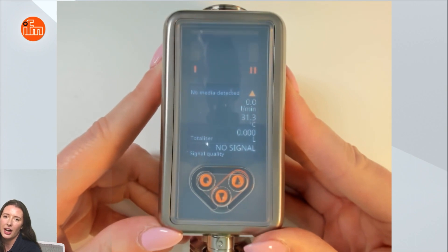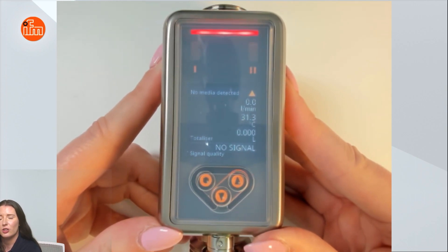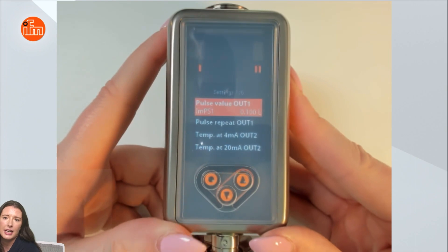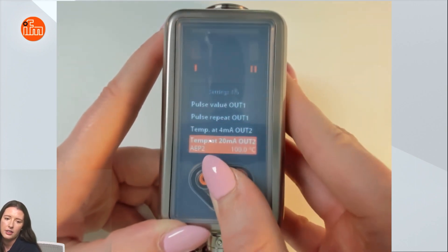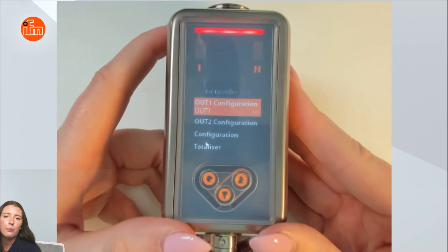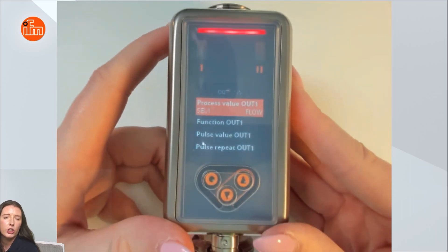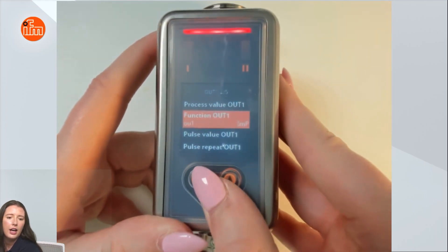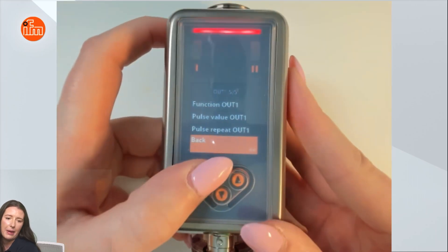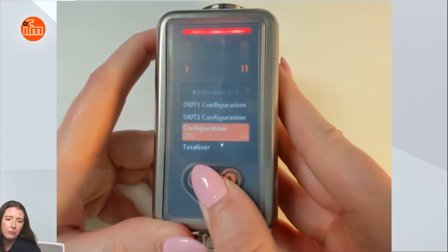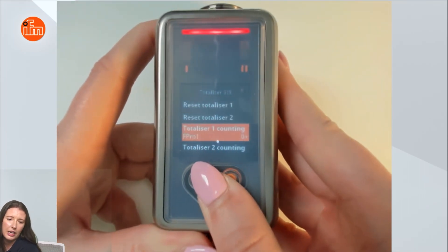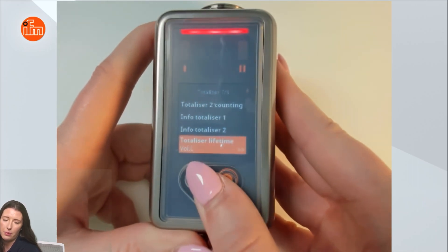After completing the installation wizard, if there are any parameters you'd still wish to change, you can go back into the menu by pressing this enter button. The first thing you will see are the basic settings of your output 1 and output 2 configurations. If you'd like to see more advanced settings, you can go into the extended functions menu by pressing enter. Here you have your output 1 and output 2 configurations, in which you could change which process value you were monitoring as well as the function of the output. To get out of this menu, you would press back. In addition, you can see different configuration menus as well as the totalizer menu, in which you could reset the totalizer value, see the totalizer count, as well as the lifetime totalizer the sensor has seen.